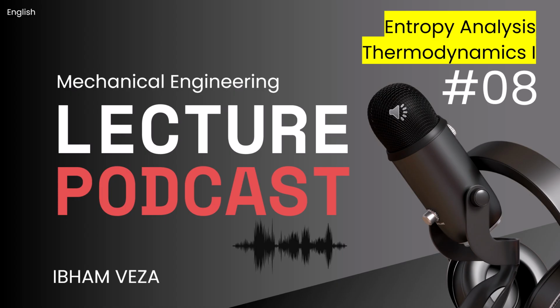So this one makes a good point. Even a 100 kilowatt motor that's 90% efficient, which sounds pretty good, 90%. Right, sounds good. But that still means 10% is lost as heat. That's 10 kilowatts of heat. It's like having a 10 kilowatt electric resistance heater running constantly. Wow. That's a lot of heat, often just dumped into the compressor room, right? Making it hotter. Often, yeah, unless it's properly vented. And that heat can then make the compressor work harder, which we'll get to.